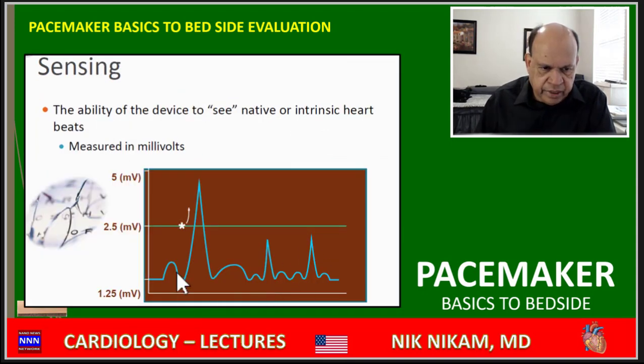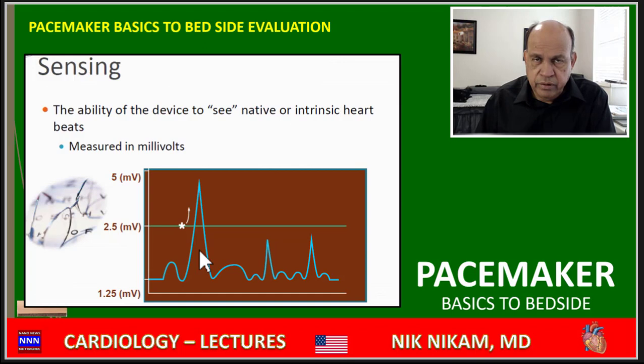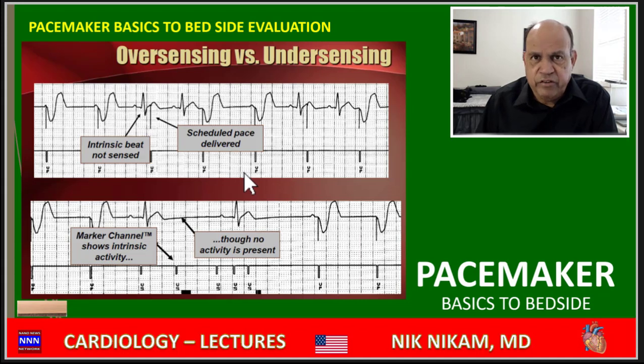Sometimes when you get an extra beat, it may throw the system off and give a wrong signal. That's why sometimes pacemakers don't recognize the premature ventricular complexes because of a significant change in the voltage. So the pacemaker may fire near the ventricular ectopic beat because it's just not able to precisely recognize those beats. Let's do some examples here.